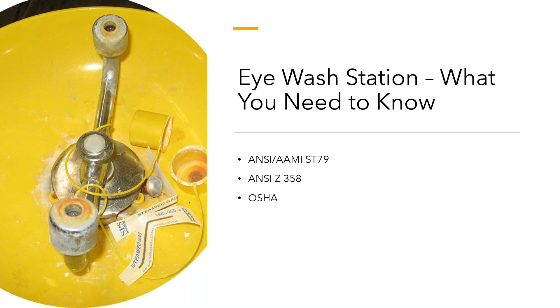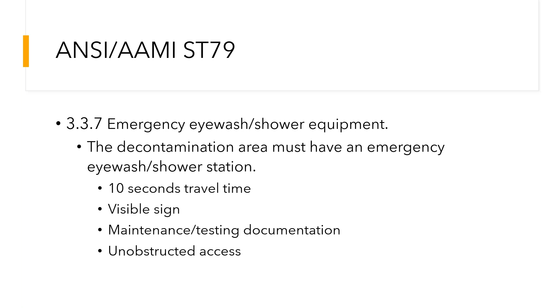ANSI, AAMI, ST79, and OSHA all have standards around eye wash stations. ANSI/AAMI ST79 requires suitable eye wash/shower equipment with unobstructed access for immediate emergency use in all locations where potentially damaging chemicals are used—cleaning solutions, disinfectants, EO, hydrogen peroxide. Pretty much anywhere in the hospital there's some possibility of chemical interaction, since every area gets cleaned by EVS. These stations need to be within 10 seconds travel time of all chemical usage locations, identified with highly visible signs, and maintained according to the manufacturer's IFU for testing and maintenance, with documentation.